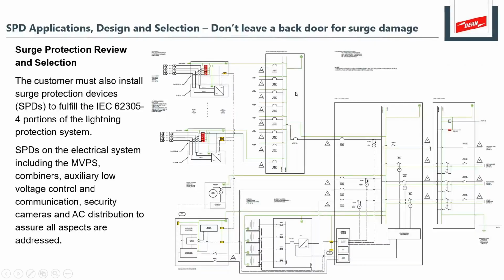We'll take a look at things like the solar industry, which is an optional industry for surge protection, but if the operators in this industry want to keep running, they're going to pay a lot of attention to the surge protection devices on the power lines, DC and AC power lines, the DC control lines, the IO lines that go back to the mains and the master control inverters, where you're watching what's going on in the panels. When panels start going bad, you have excessive currents and voltages because it's trying to keep up with the rest of the panels and regulate its voltage, and it causes stresses in all of the collection systems.